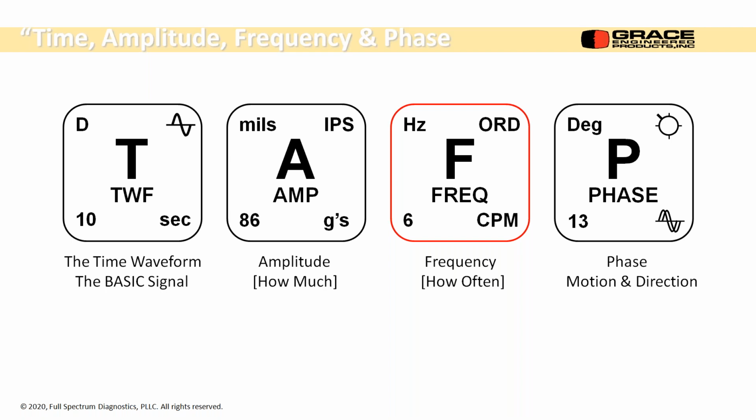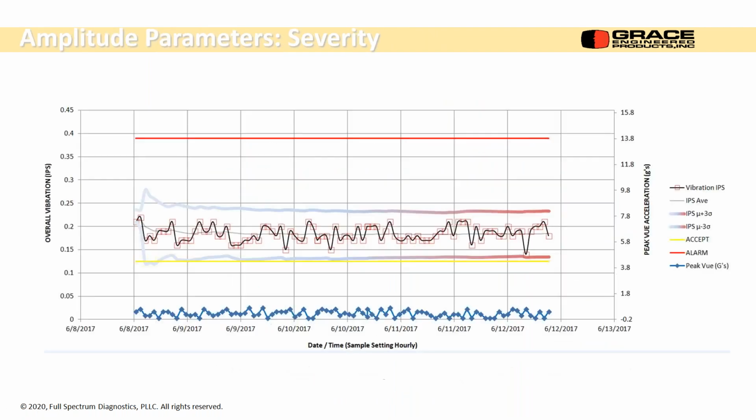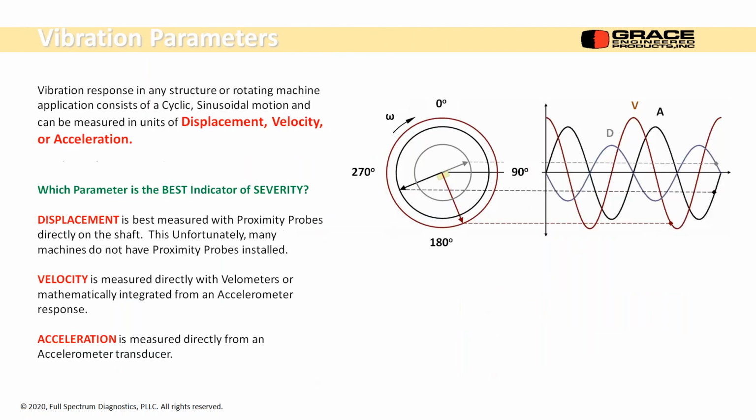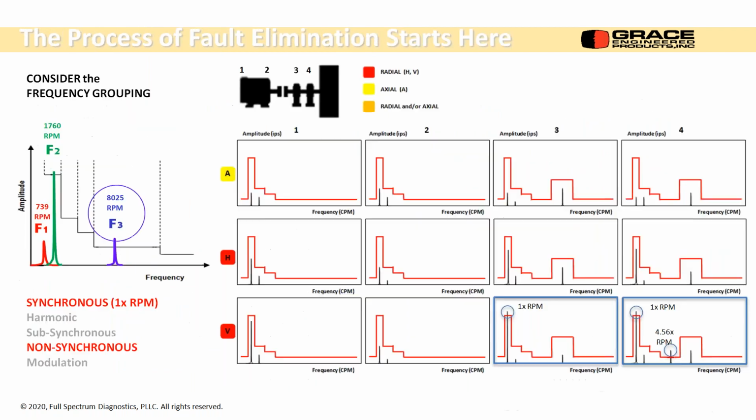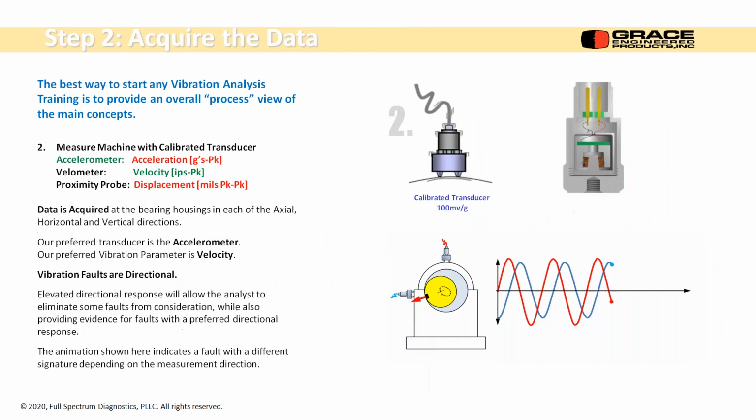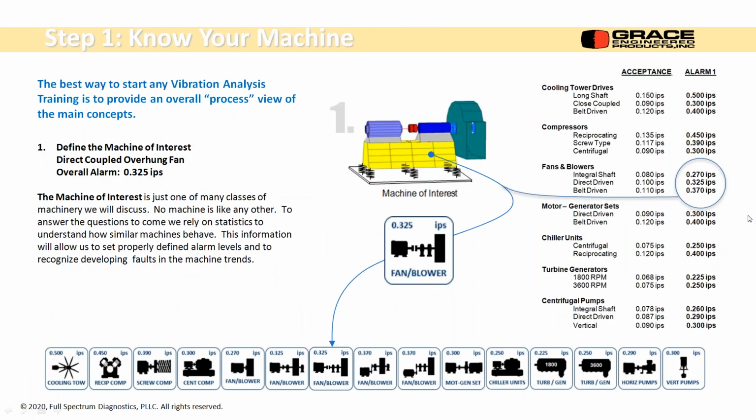No, the motor really doesn't exist anymore as far as being of interest. On this list, you have a piece of equipment. It's whatever the motor's driving. That's what you set the alarms for. And then the motor themselves, you give them the same alarms.